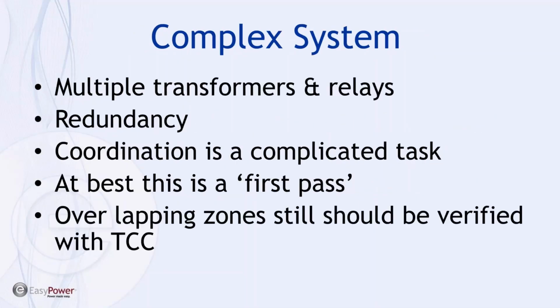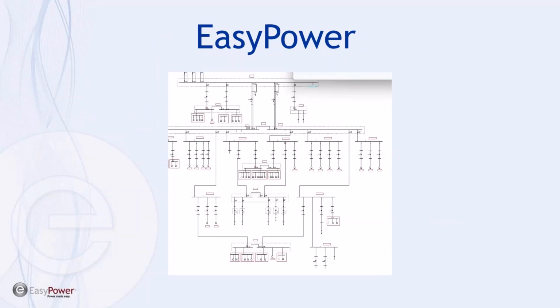So again, I'm going to be jumping into this complex system that has multiple transformers and relays, a fair amount of redundancy. Coordination is a complicated task at best. And what you're going to see is what I felt was a pretty good first pass at coordination, at least for one value. And then clearly, once you see what I've got going on, it will be necessary to go back and check overlapping zones for relays to make sure that there's not some miscoordination other than the current that we checked. Okay, so let's jump into EasyPower and see how this goes.